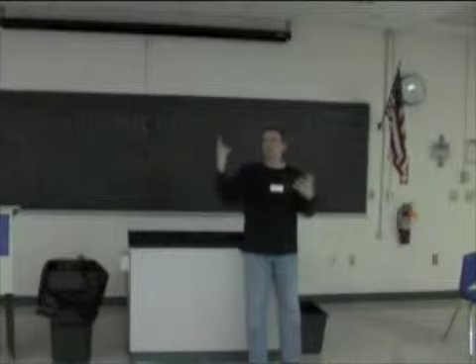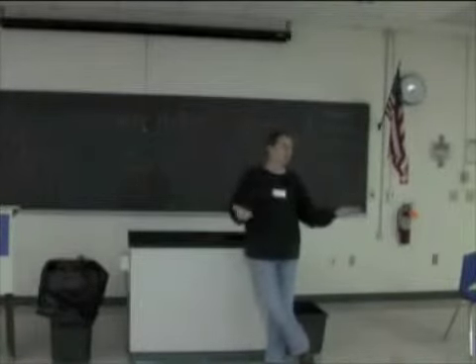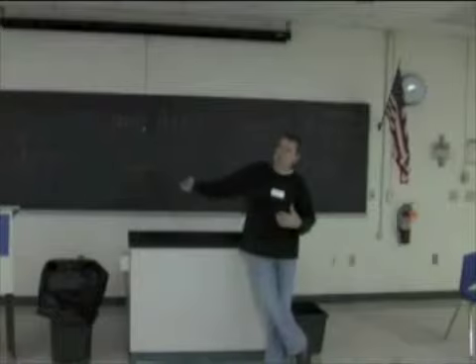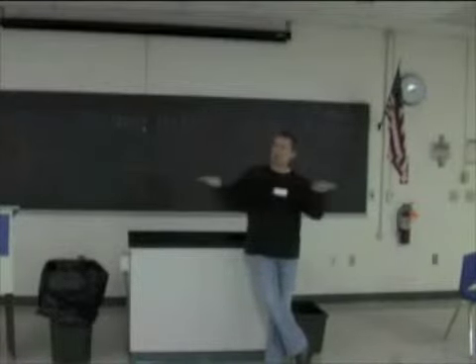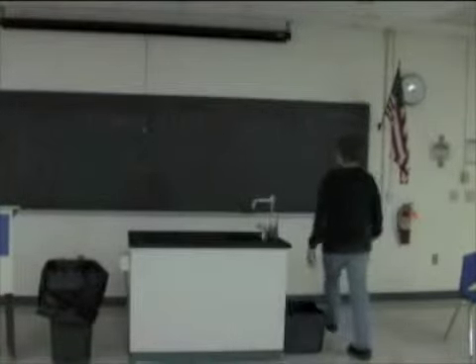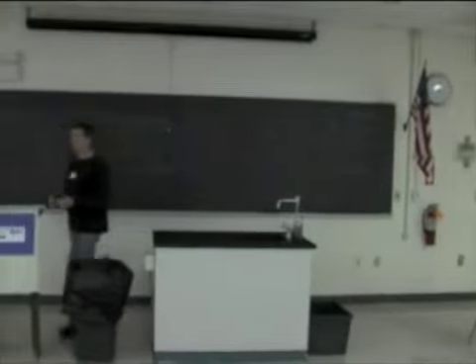And if it's only 1 day a year or 1 hour a day that you reach that peak, they have to somehow recuperate, they have to get their money back. And so what they do is they bill you based on your demand. I've seen electric bills where the demand is the same price as the generation. And so if you could shave off the demand, you could save 50% of the electric bill. And if you're talking about a building like this that's paying $500,000 or $200,000 a year, now you're talking about a real significant amount of money.